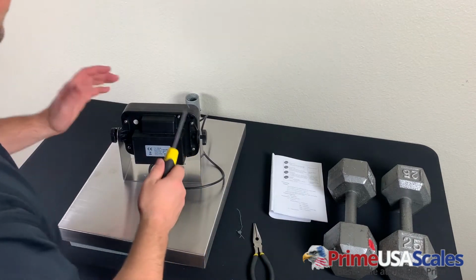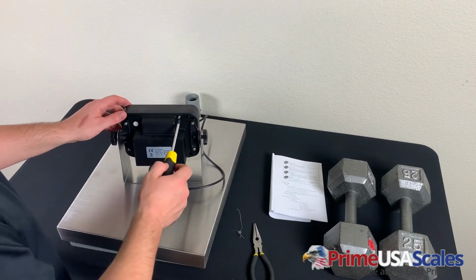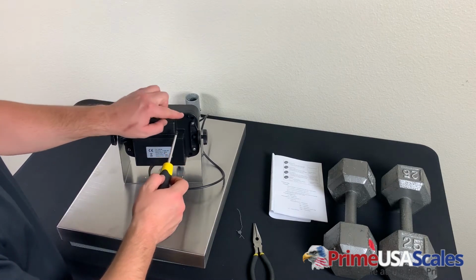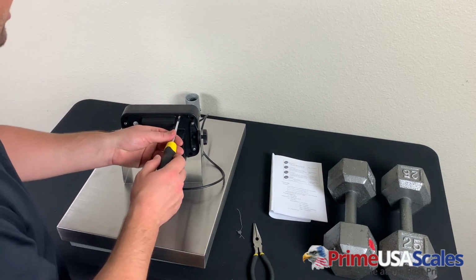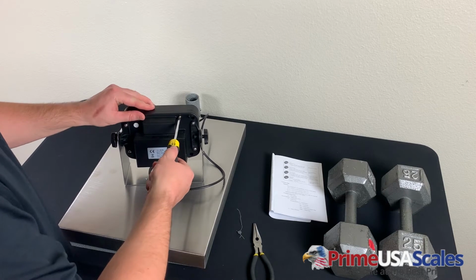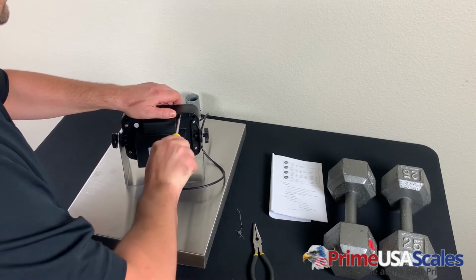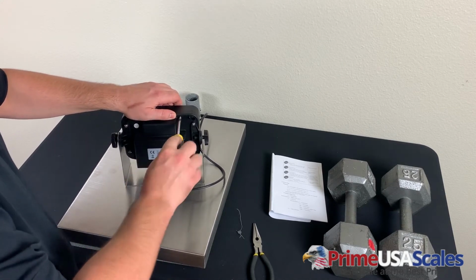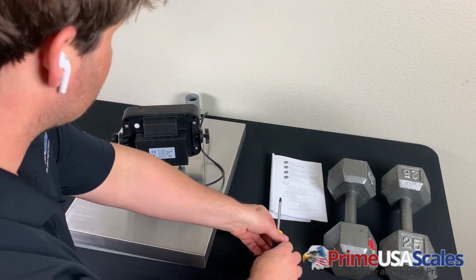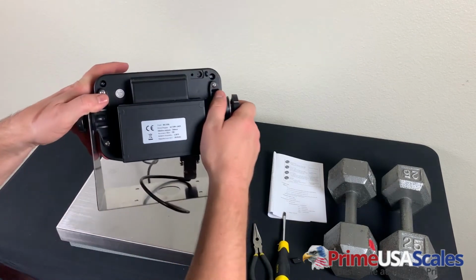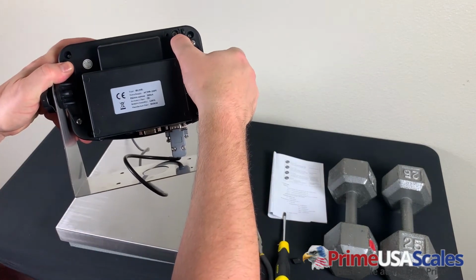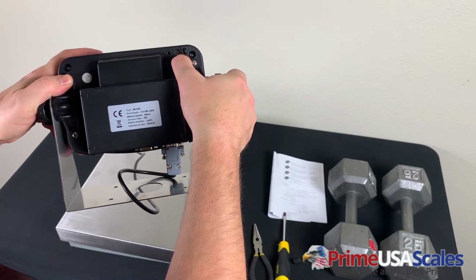After we've removed our lead seal, the next step is going to be to take off this screw here to access the calibration button. So we'll take a screwdriver and we'll loosen this in order to get access. And just to give you guys a close-up shot, here you can see is the button that will put us into calibration mode.